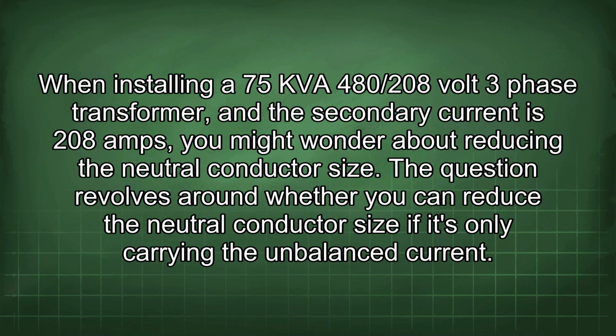When installing a 75 kVA 480/208 volt three-phase transformer, and the secondary current is 208 amps, you might wonder about reducing the neutral conductor size. The question revolves around whether you can reduce the neutral conductor size if it's only carrying the unbalanced current.